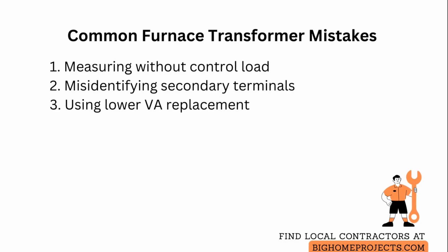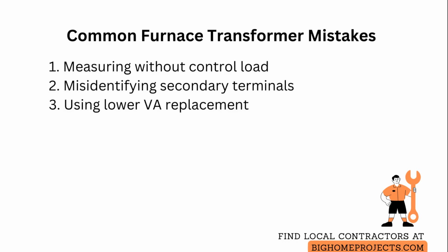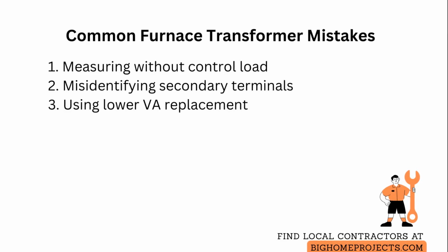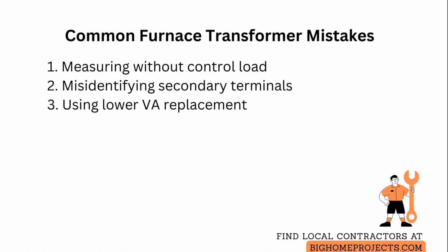Third, using an incorrect replacement transformer with a lower volt-ampere capacity causes repeated overloads and premature failure. Always match or exceed the original transformer's volt-ampere rating and verify the secondary voltage is the same.